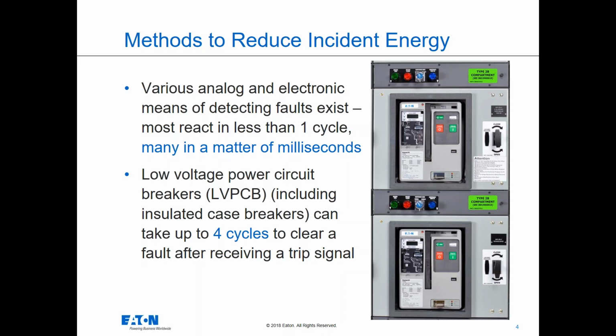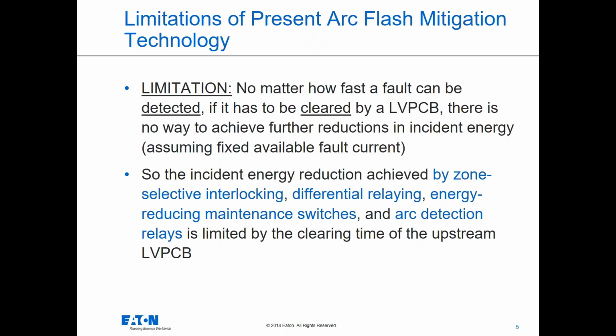Low voltage power circuit breakers, per UL standards, can take up to 4 cycles to physically clear a fault after it receives a trip signal. So in terms of an electrical arc fault, that's kind of an eternity, right? So if I have a trip unit that basically reacts in 0 time, I still may have to wait up to 4 physical cycles for the mechanism of the breaker to physically open. So that's a physical limitation of the mechanical systems that are built into the circuit breaker.